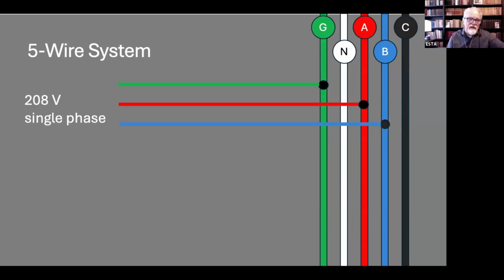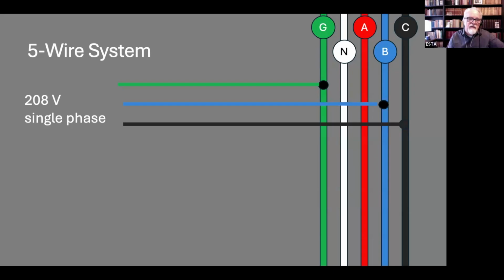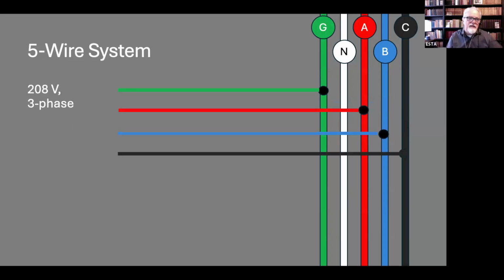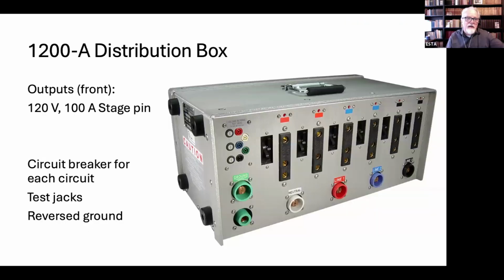So you can also get 3 208-volt circuits by connecting any phase to any other phase. So phase A to B gives you 208 volts. Phase A to C gives you 208 volts. Phase B to C gives you 208 volts, right? So that's 2. We got 120 and we got 208. We also can get 3-phase. This is for motors, right? By connecting just between the phases, no neutral. And notice that there's always a ground.